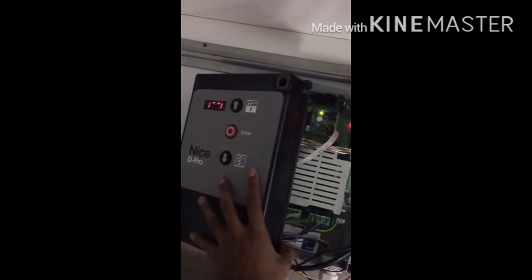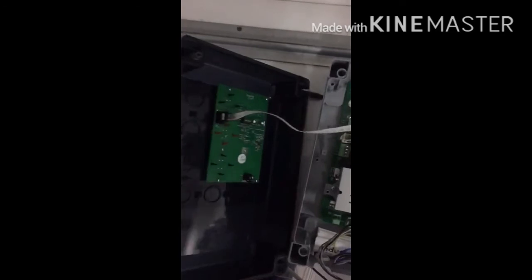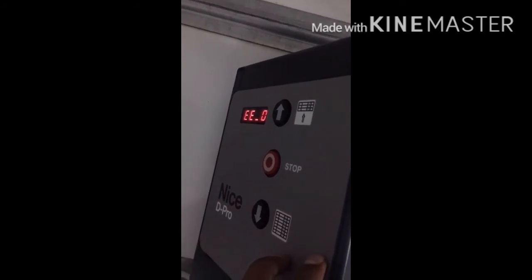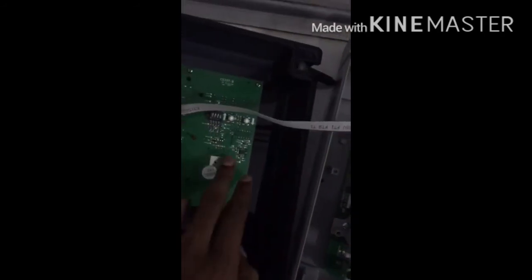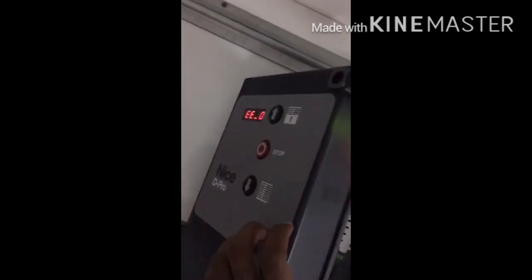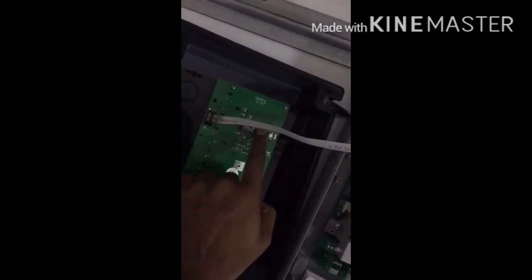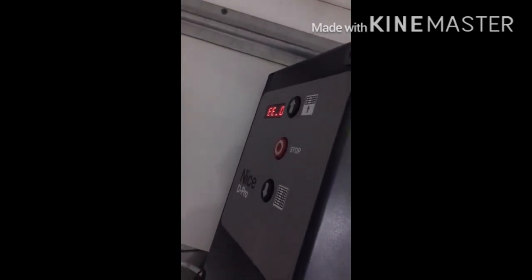For completely resetting the Nice D-Pro automatic control unit, you need to switch on DIP numbers one, two, and three. The display should show 800. Press the open and close buttons together — it will show dashes. Make sure it shows EE0. If it shows EE1, press the down key to make it zero. Once it shows EE0, press the open and close buttons together to complete the reset.